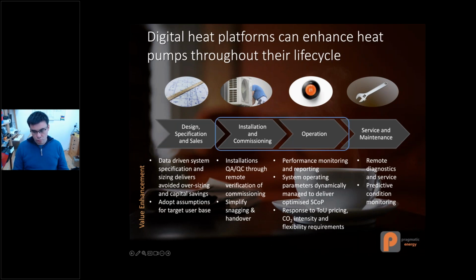Rachel talked about it as remote diagnostics. I think that's a pretty broad term, but from the point of view of what's missing, it's digital tools that take advantage of all the data flowing from a heat pump or heat store to make sure the installation's done properly—providing quality control and quality assurance, remotely verifying the heat pump has been physically installed okay, commissioned okay, but perhaps most importantly, that all the digital settings within the heat pump have been configured appropriately for that installation and site.